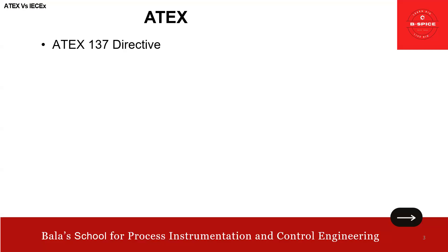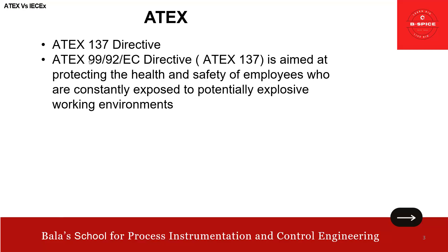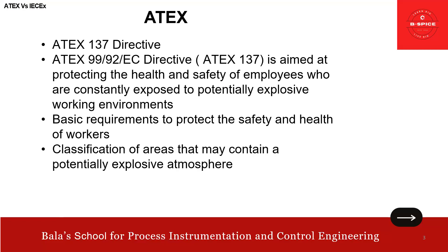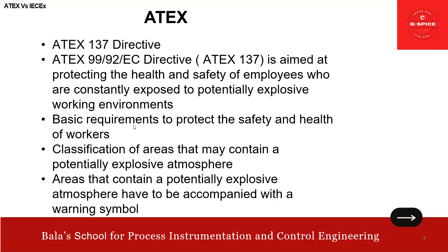We have one more directive: the ATEX 137 directive, also called the ATEX 99/92/EC directive. This is aimed at protecting the health and safety of employees who are constantly exposed to a potentially explosive working environment. It states the basic requirements to protect the safety and health of workers, classifies areas that may contain a potentially explosive atmosphere, and states that such areas have to be accompanied with a warning symbol.